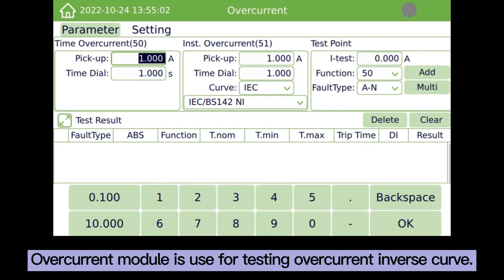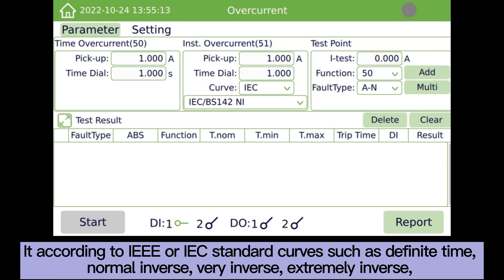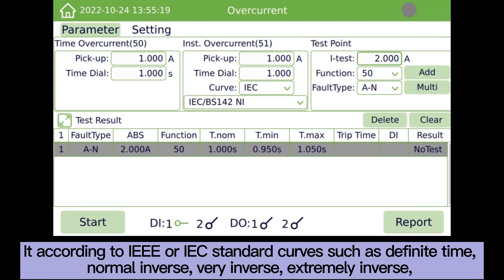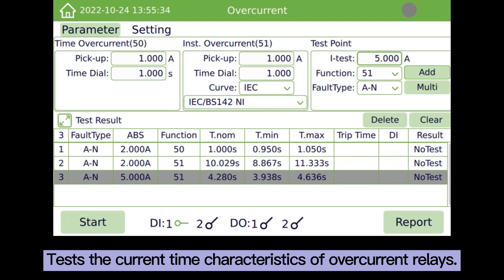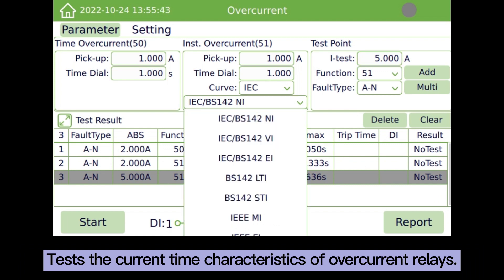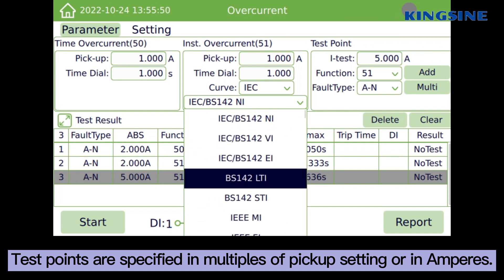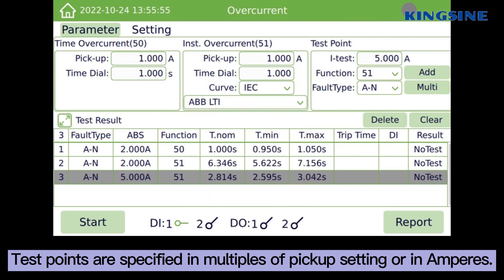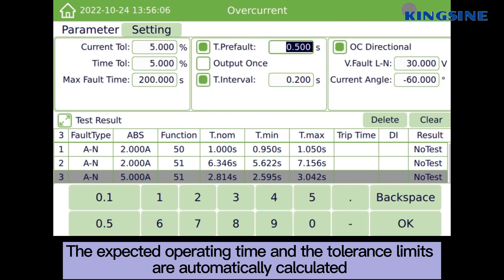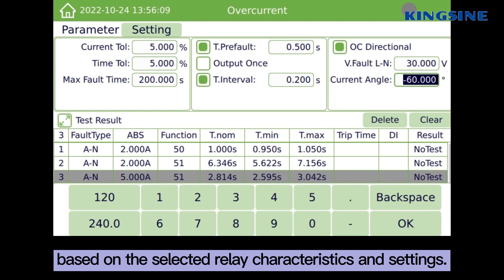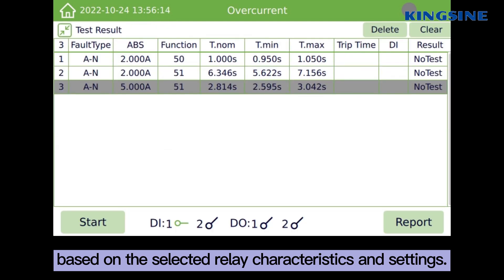The overcurrent module is used for testing overcurrent inverse curves. It follows IEC standard curves such as definite time, normal inverse, very inverse, extremely inverse, or other predefined inverse curves, to test the current-time characteristics of overcurrent relays. Test points are specified in multiples of pickup settings or in amperes. The expected operating time and tolerance limits are automatically calculated based on the selected relay characteristics and settings.